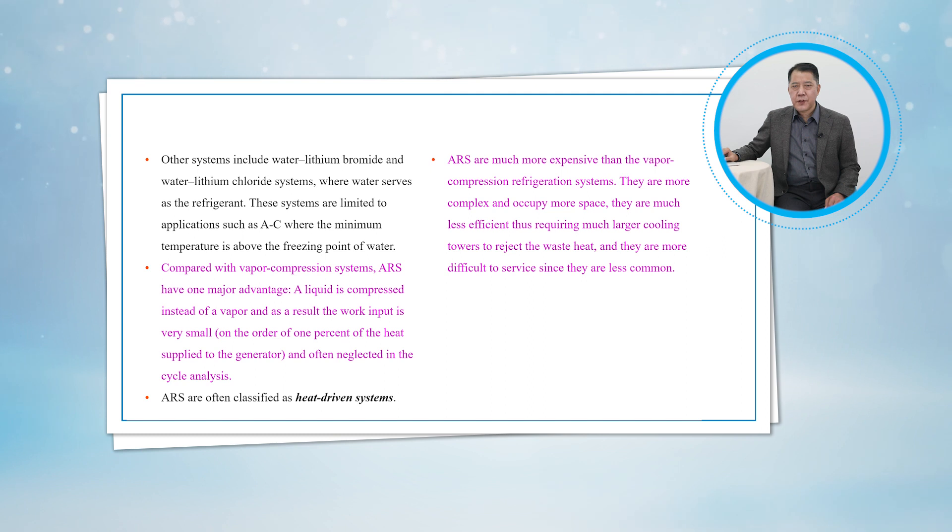The absorption refrigeration systems are much more expensive than the vapor compression refrigeration systems. They are more complex and occupy more space. They are much less efficient, thus requiring much larger cooling towers to reject the waste heat, and they are more difficult to service since they are less common.